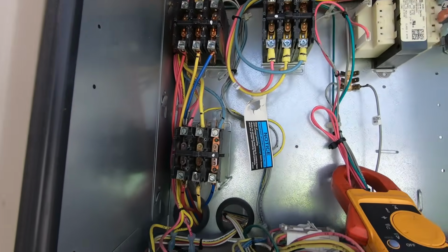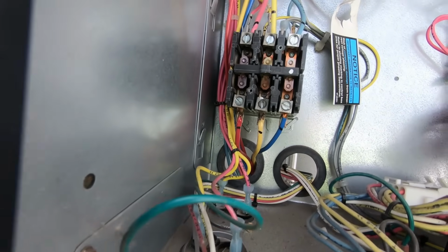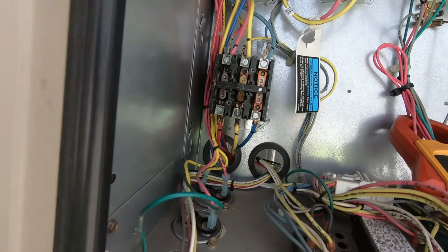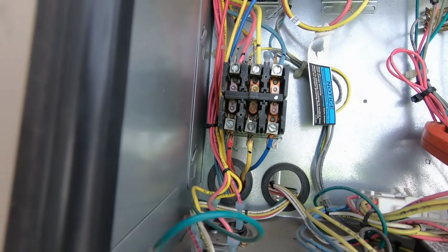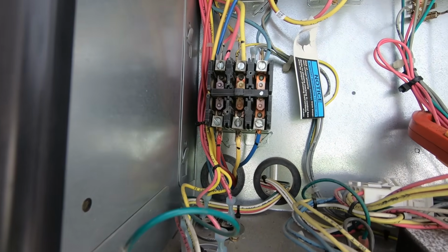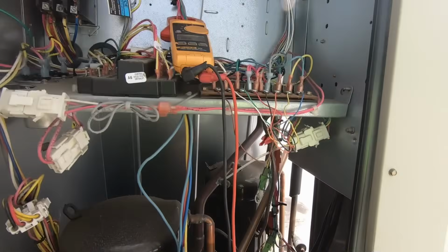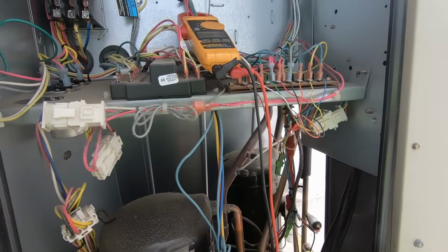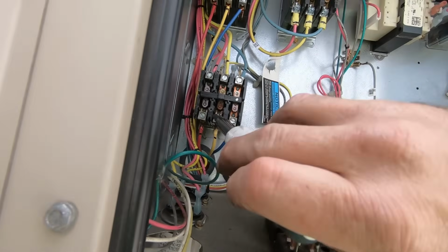Well, I'm looking over these contactors, and I'd say we've got an issue with this guy. At least the wires are melted, the contacts are burnt and very pitted. Looks like it got awfully hot. Just curious if we had loose connections here.